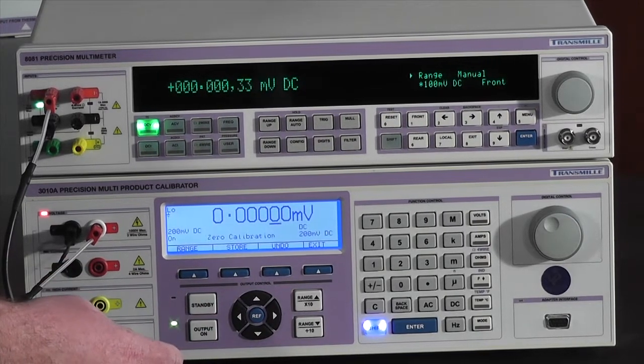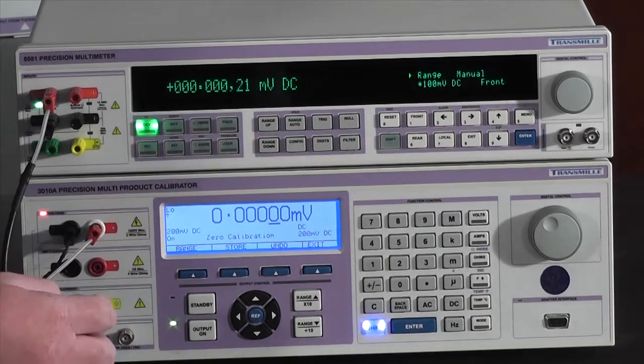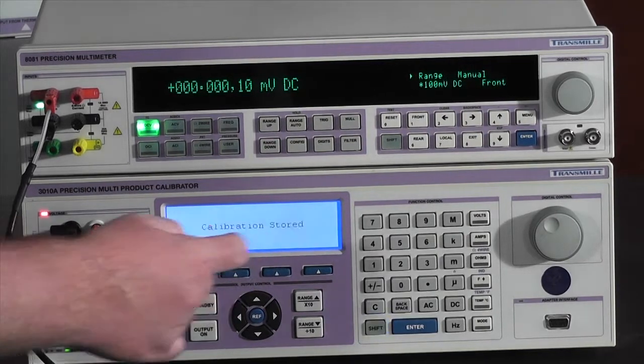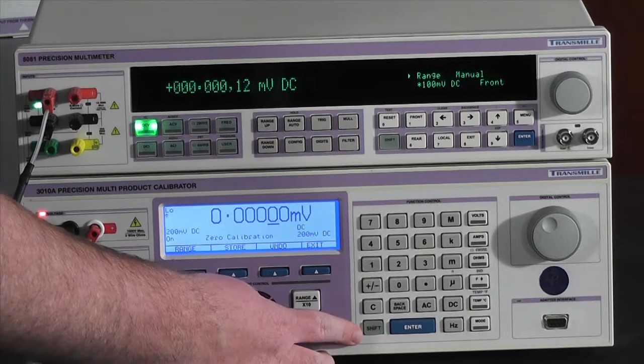I make a smaller adjustment just to get as close to zero as I can. I'm then going to press store and the calibrator will indicate that the new calibration has been stored and the shift light will go out.